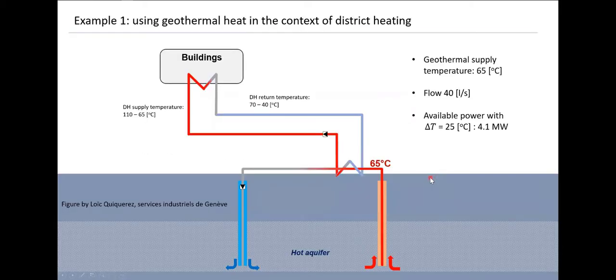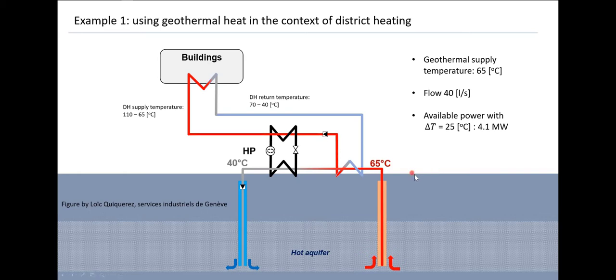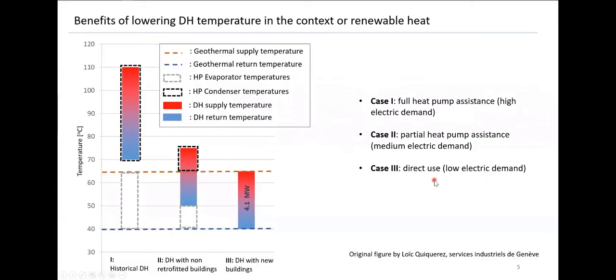We suppose here that we have a geothermal resource with a temperature level of 65 degrees and a flow rate of 40 liters per second. If we are able to achieve a delta T of 25 degrees — meaning we re-inject the water at 40 degrees — this will lead to a thermal power of 4.1 megawatt. Depending on the operating levels of the district heating, we may require assistance from a heat pump.